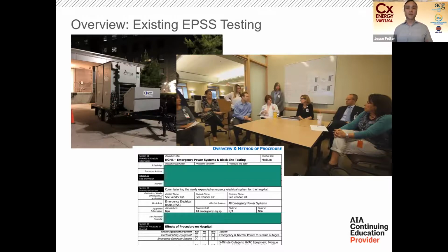Maybe there's a concern for an event—a medical event, an emergent event, a life flight or an ambulance, an unscheduled surgery. What if we can tell the client, the facility operations individual, that we can back out of the test in six minutes? We put somebody at your hip at the head nurse's station, and if they say stop the test, we can get out of this test and restore to normal operation in six minutes, or whatever it may be for your facility.